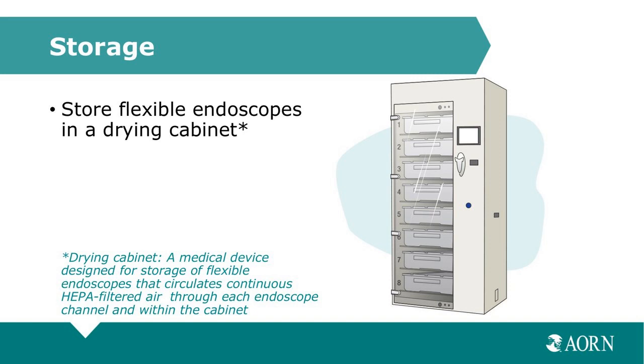AORN recommends that your processed flexible endoscopes are stored in a drying cabinet. And again, the collective evidence tells us that optimal storage of flexible endoscopes provides protection from environmental contaminants. Now, drying cabinets include a drying system that circulates HEPA-filtered air through the cabinet, while filtered air under pressure is also forced continuously through those endoscope channels. So the internal and the external surfaces of the endoscope are being continuously dried, and this will suppress bacterial growth.